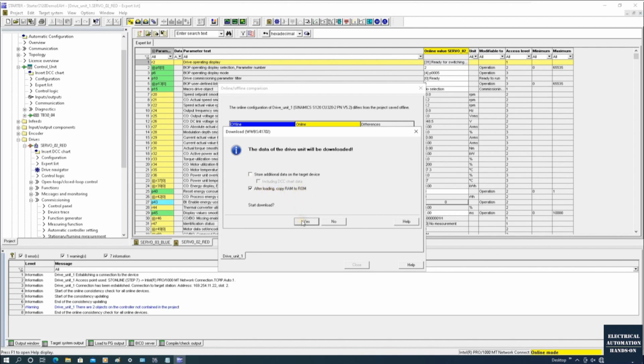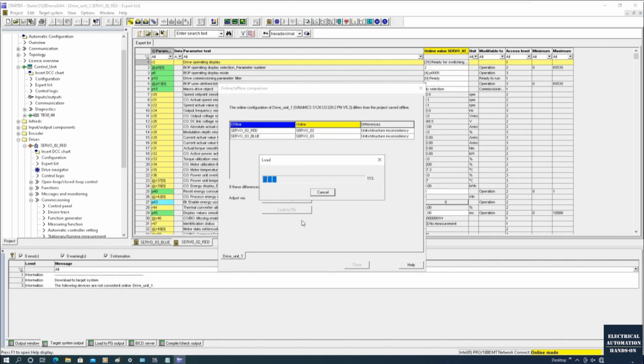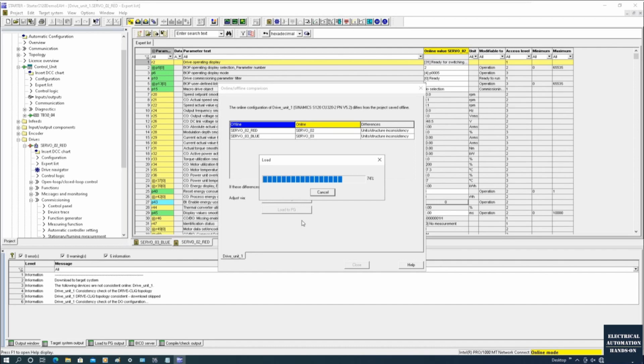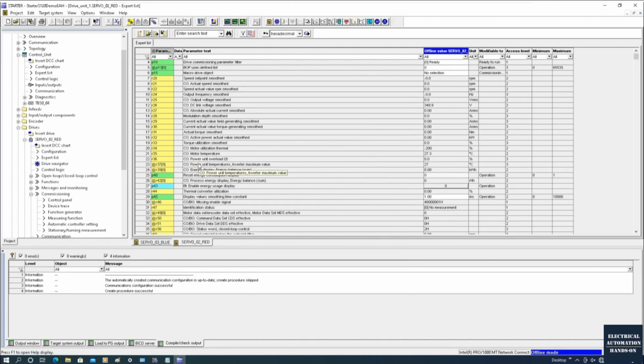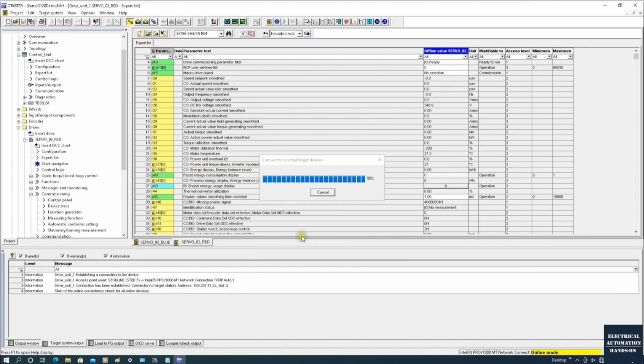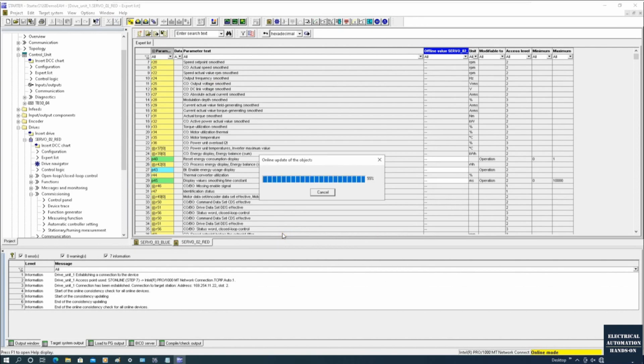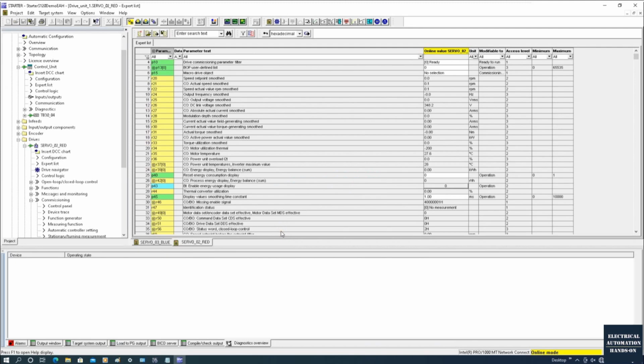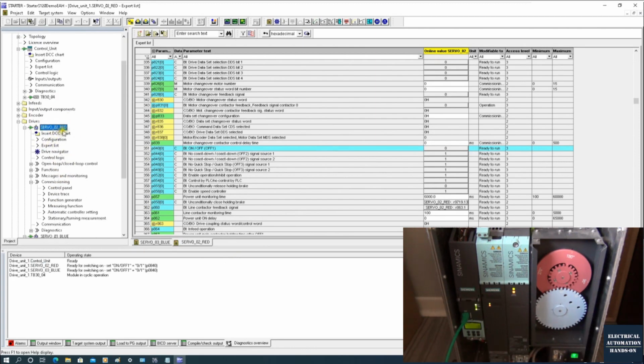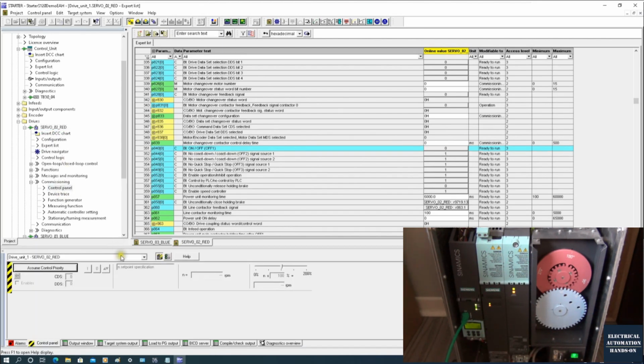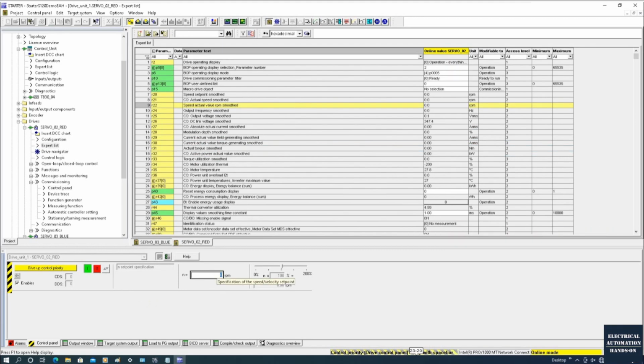Okay, we can select this copy RAM to ROM to save all the parameters to the ROM. So once we shut down the power, it still works. Okay, now let's go online again. Okay, we go online again. And now let's commission this drive, the red axis first. So double click this motor panel. Okay, red motor. Assume control priority. Enable the power. And then let's set 60.